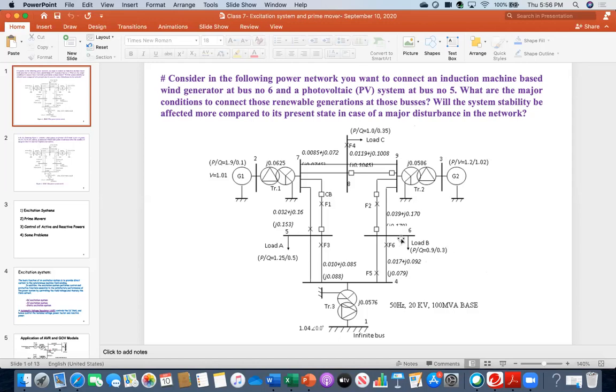The frequency should be the same. Here it is 50 Hertz. Accordingly, you have to choose a 50 Hertz system. Otherwise, you cannot connect it here. Also, the phase angle should be the same. For example, at this bus, there is a voltage magnitude, 20 kV RMS value. Let's say it has a phase angle of 5 degrees. So once you connect that system, that should also have the same phase angle.